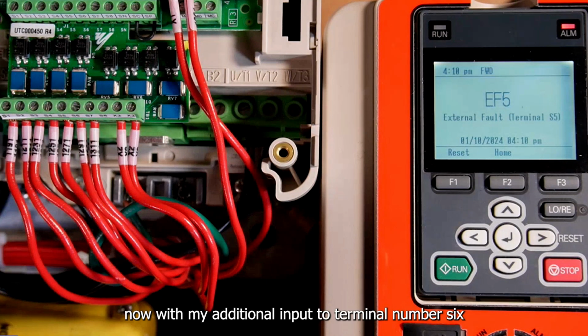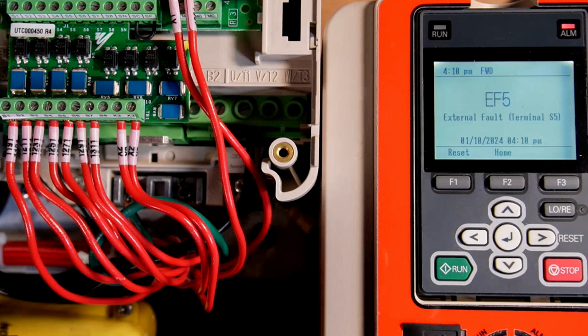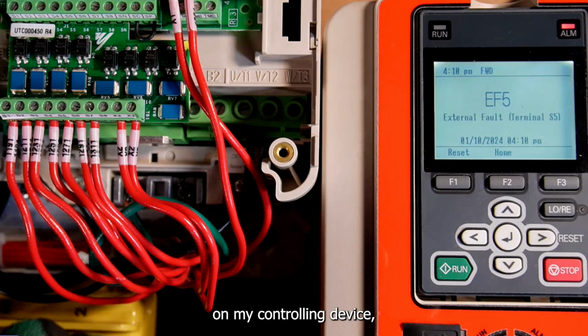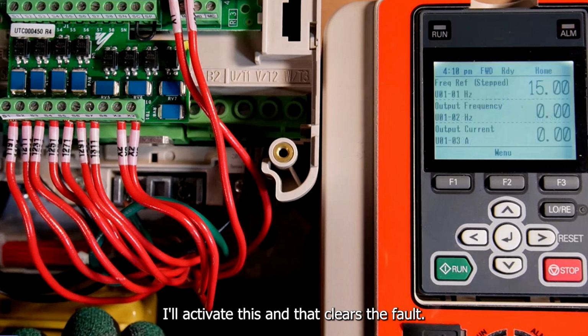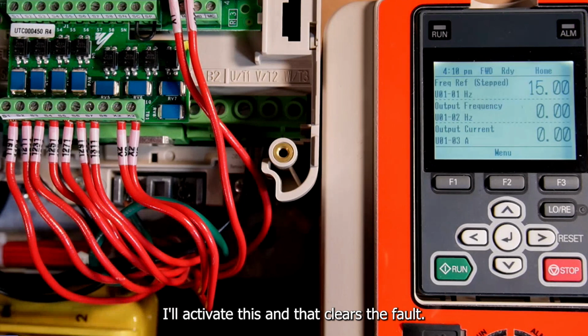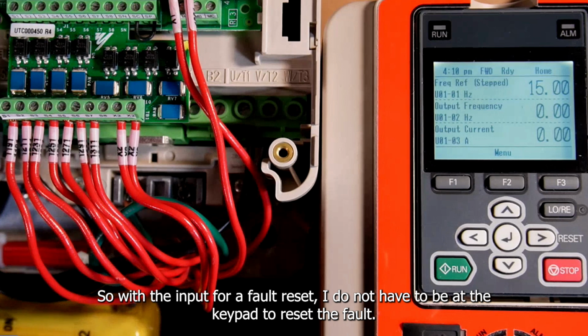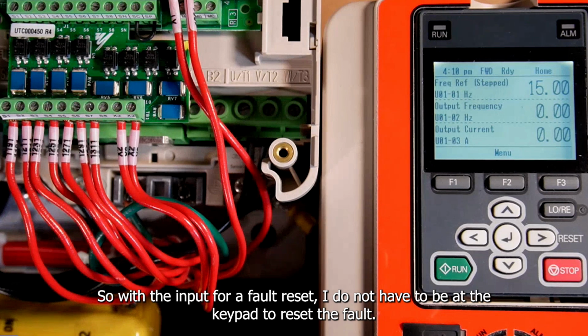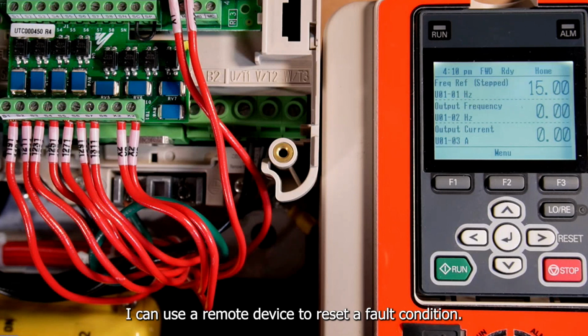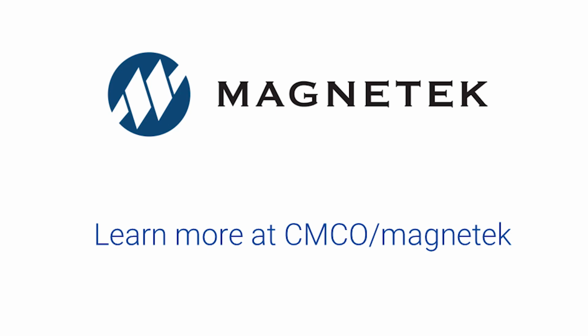But now with my additional input to terminal number 6 on my controlling device, I'll activate this, and that clears the fault. So with the input for a fault reset, I do not have to be at the keypad to reset the fault. I can use a remote device to reset a fault condition.